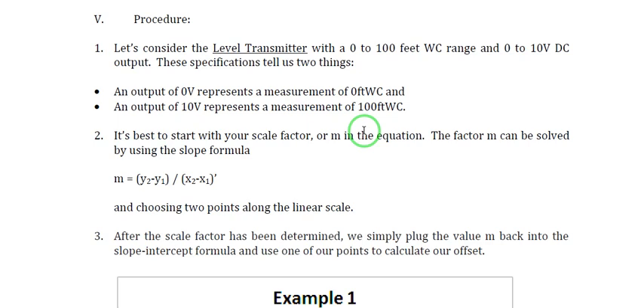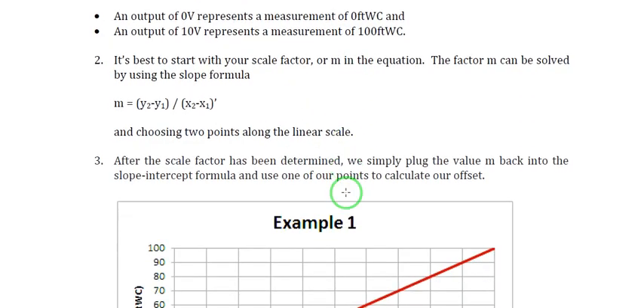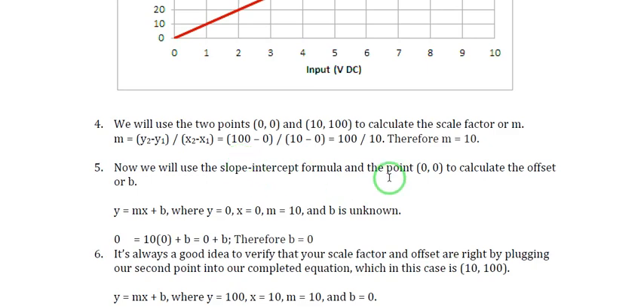So using the two-point form, we are going to determine our slope by substituting the values. Our Y will be the value of our water level. Then our X is our direct voltage output of the level transmitter. In which case, we get a slope of 10.